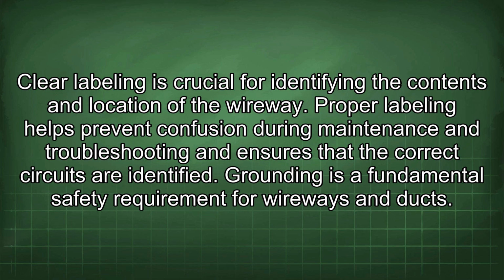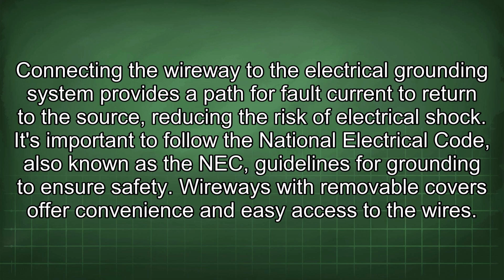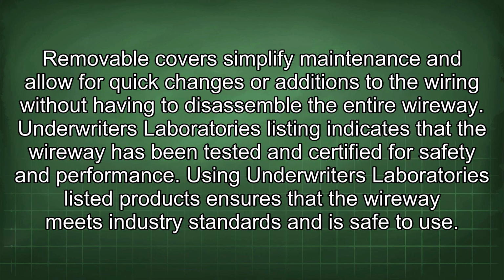Grounding is a fundamental safety requirement for wireways and ducts. Connecting the wireway to the electrical grounding system provides a path for fault current to return to the source, reducing the risk of electrical shock. It's important to follow the National Electrical Code, also known as the NEC, guidelines for grounding to ensure safety. Wireways with removable covers offer convenience and easy access to the wires. Removable covers simplify maintenance and allow for quick changes or additions to the wiring without having to disassemble the entire wireway. Underwriters Laboratories listing indicates that the wireway has been tested and certified for safety and performance.